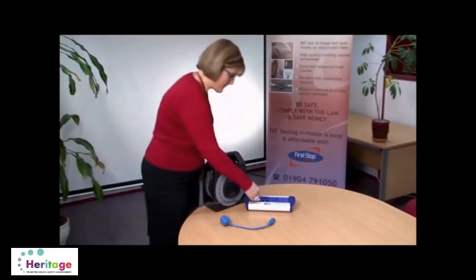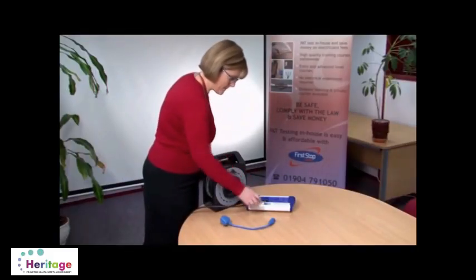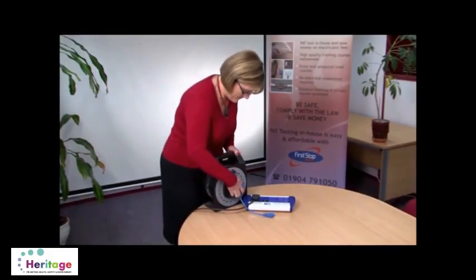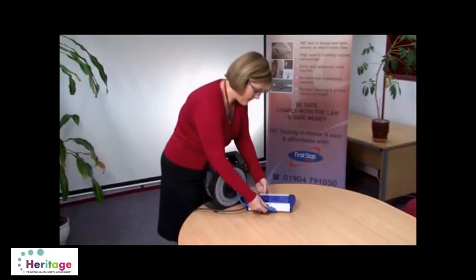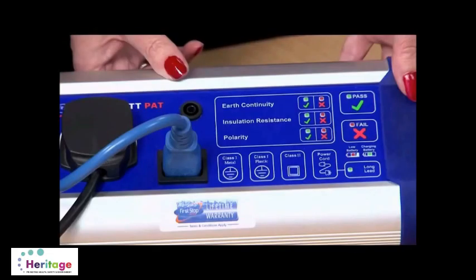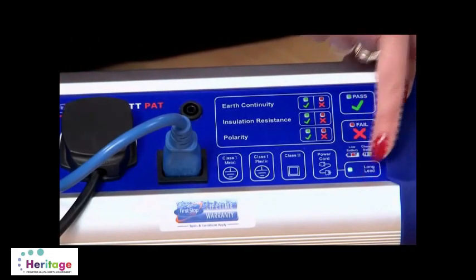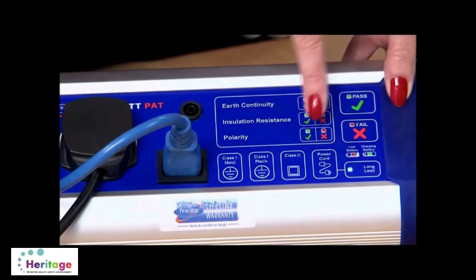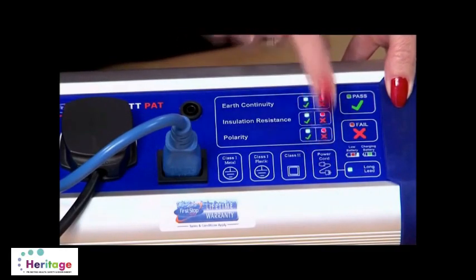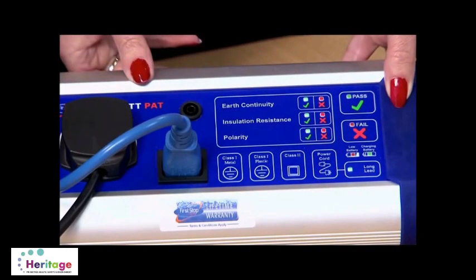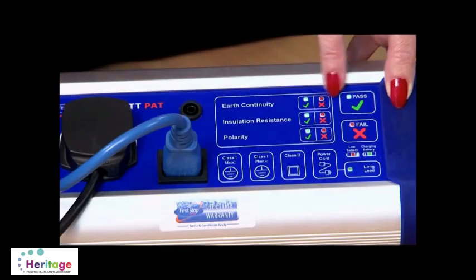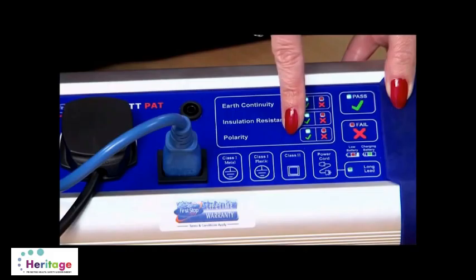Testing a long mains extension lead. Plug the mains extension lead into the BAT-PAT. Connect the short IEC lead to the socket of the mains extension back to the PAT tester as shown. Press the long lead button and then press the power cord button and wait for the BAT-PAT to display the results of the earth continuity, insulation resistance and polarity tests.